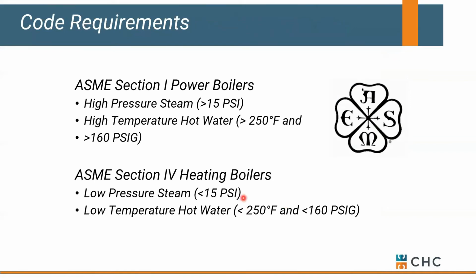Commercially, we tend to operate with steam boilers that are less than 15 pounds and water boilers that are less than 160 pounds of max working pressure and output temperatures less than 250 degrees. If you're dealing with industrial, you're typically dealing with higher pressure steam and potentially higher pressure hot water. Okay, but commercial world, we tend to spend a lot of time in section 4. Not that means much to you. If you get out of section 4, you're probably going to have a dedicated operator in your mechanical room to keep an eye on that boiler every time it's firing or in operation.